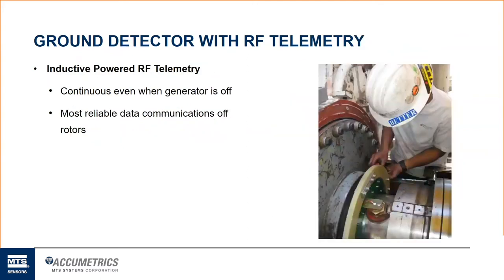So the next style is ours, ground fault detection using radio frequency telemetry. Ours is induction powered. What that means is we're bringing the necessary power across a wireless air gap out to the rotor mounted transmitter that powers our electronics out on the transmitter. And in turn, it sends a data signal across that air gap back to the stationary side to let us know what the field voltage is and the field resistance out on the generator.